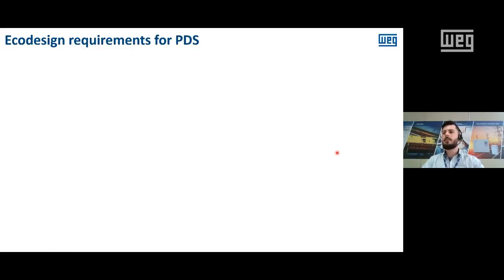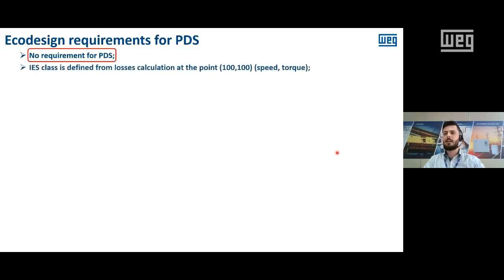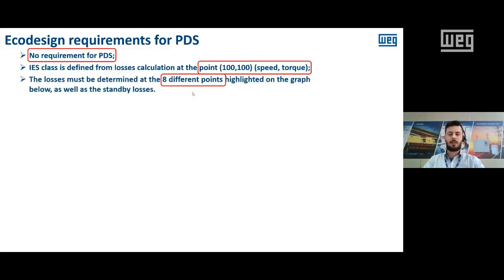Okay, so we also have the power drive systems. One thing interesting: the regulation does not require an efficiency level for power drive systems, although the IES class is defined by using some loss calculations at the point of 100% speed and 100% torque. And therefore, if they define this level, you can go and see if your PDS is IES1, IES2. So this is still important, even though it's not a clear requirement. Perhaps in the future it's going to be a requirement, but until now there is nothing requesting that.